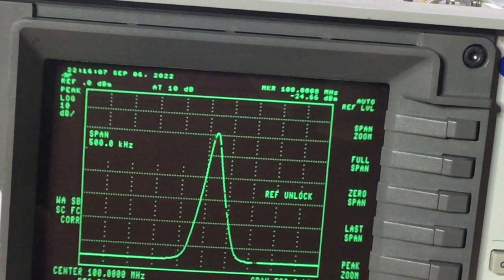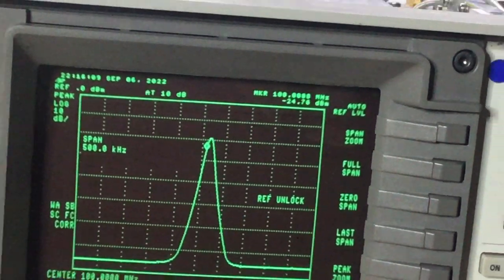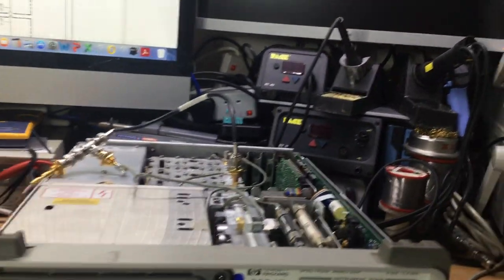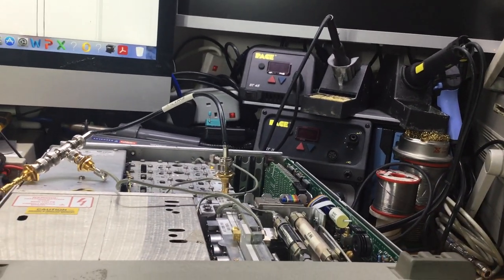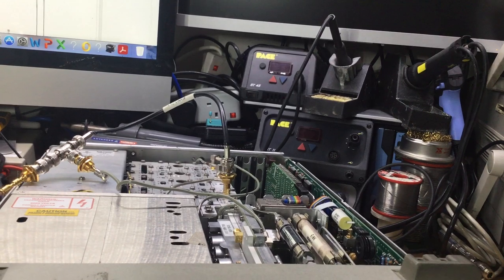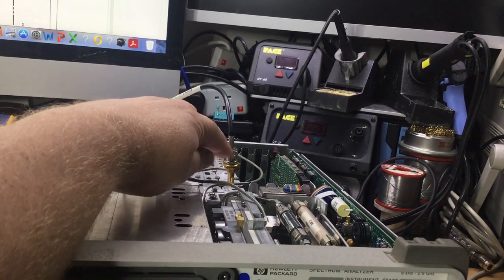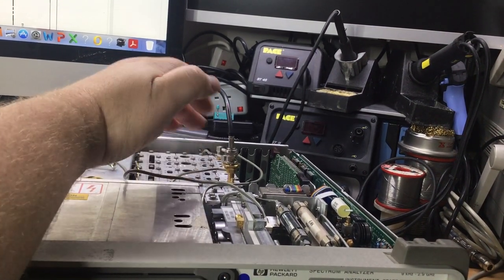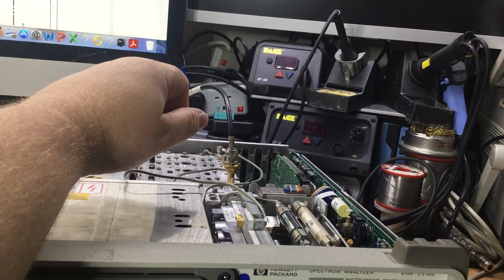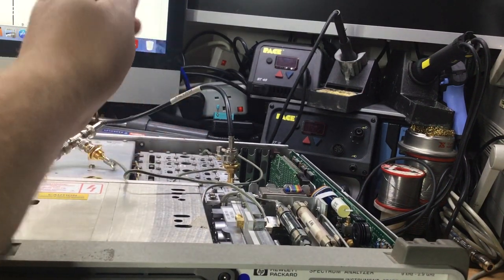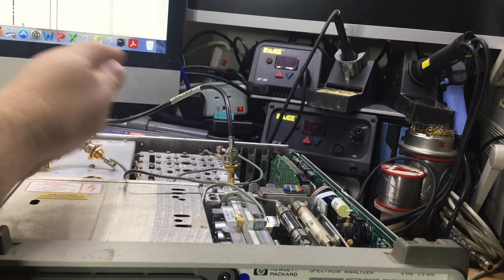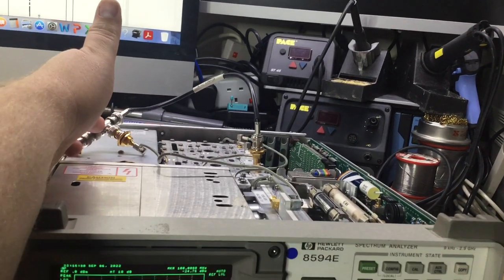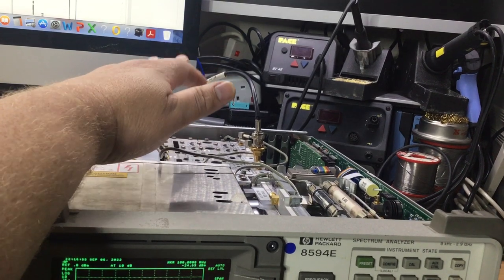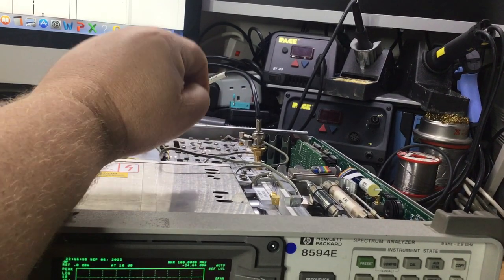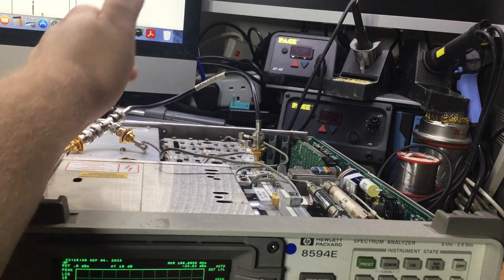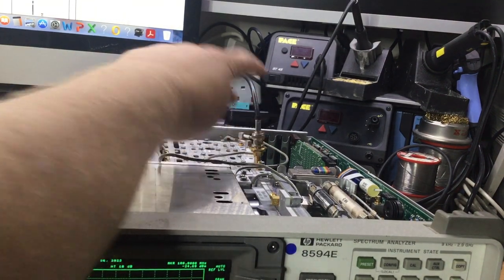So basically what I've done, I'm intercepting right now the point between the third converter and the second converter. This is where the 600 megahertz signal escapes the third converter and then enters the second converter for mixing with the RF input signal. So we've teed off, we've basically got a tee here. And we're not interfering with the connectivity between the third converter and the second converter, the 600 megahertz output, which is from this socket here.